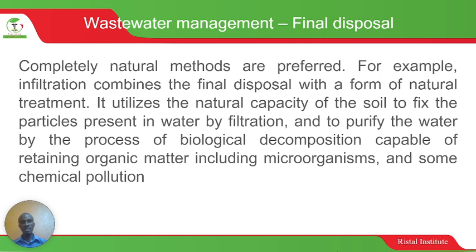So the final disposal is going to utilize the natural capacity of the soil to fix particles present in water by filtration, and then purify the water by the process of biological decomposition. Like I said, the soil where you're disposing of this wastewater should contain some microorganisms that are going to break down the organic matter in this wastewater, so that it doesn't cause environmental and human health problems.